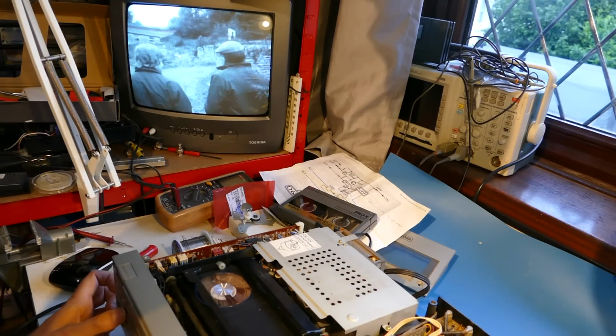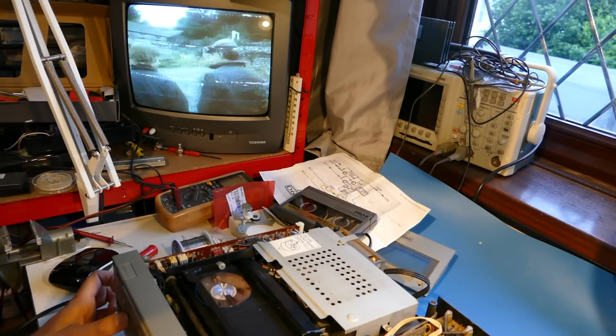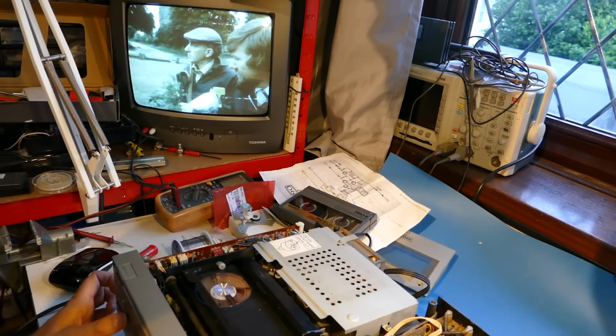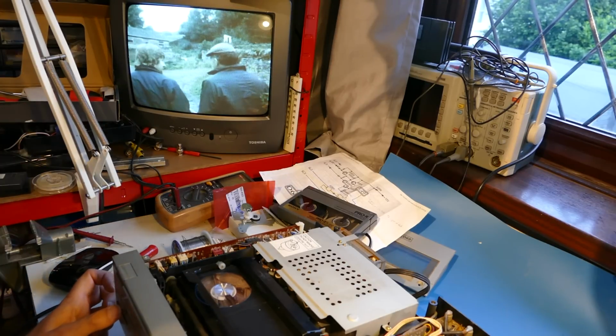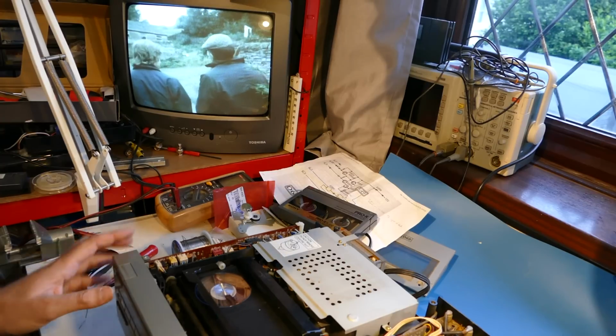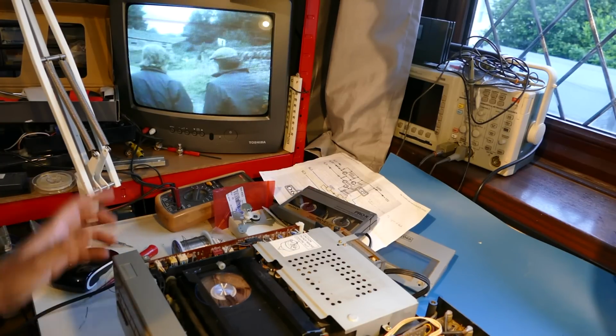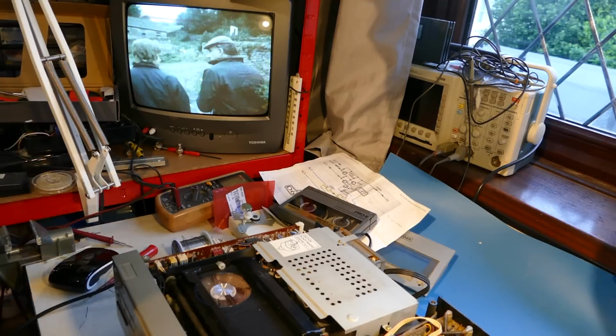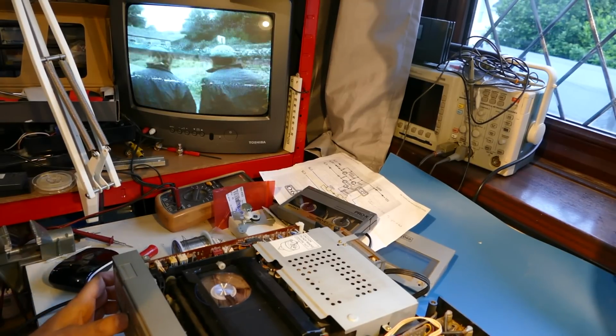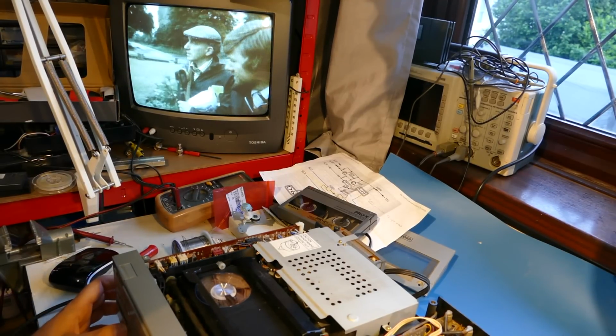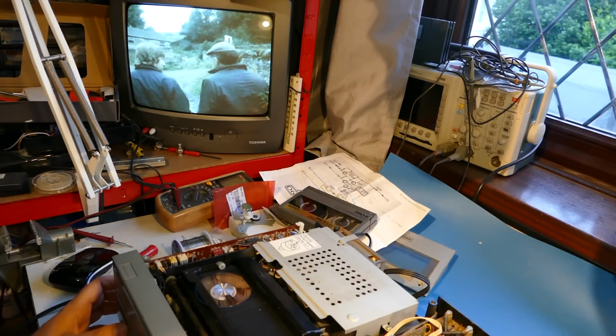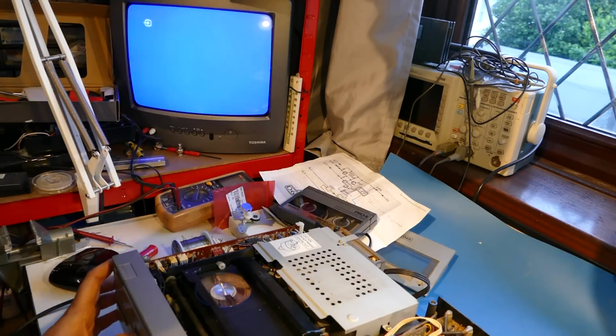Dropout, dropout, dropout, good, right? Dropout, dropout, dropout, good. That shows us the dropout compensator is working well on this machine. If you got those white flashes all the time, that would imply the dropout compensator needs adjustment. It's working well on this machine, no need to adjust that.